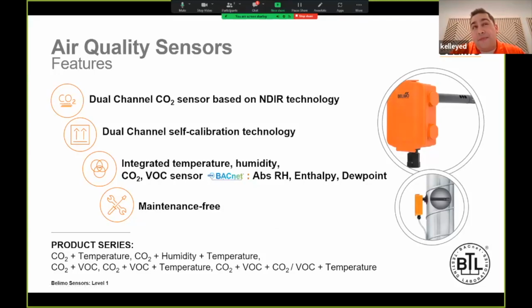There's kind of 2, let's just say, background algorithms that combat drift in real time. So when sensors get installed into an application and air starts to run through a sensor, it gets dirty. As the sensor gets more dirty over time, it starts to drift away from its manufactured stated accuracy and so on. ABC Logic has been around for a long time. We've now standardized on dual channel and NDIR.